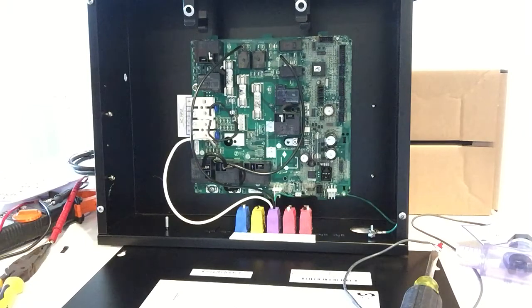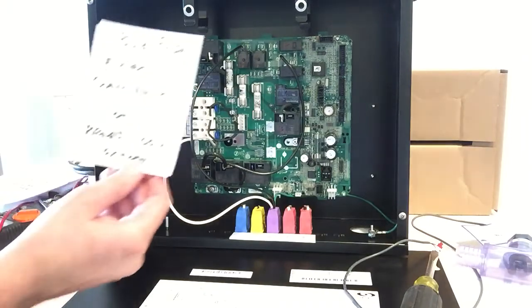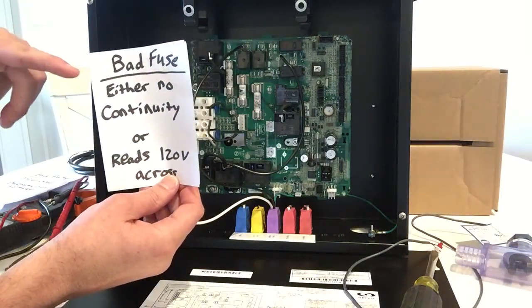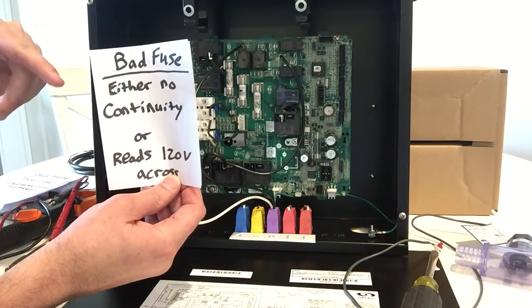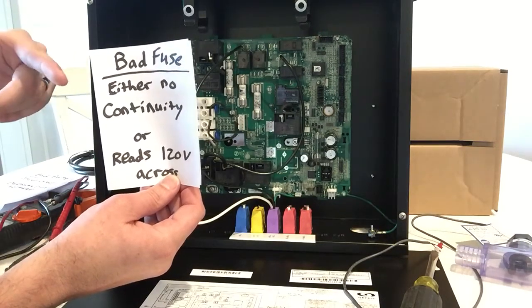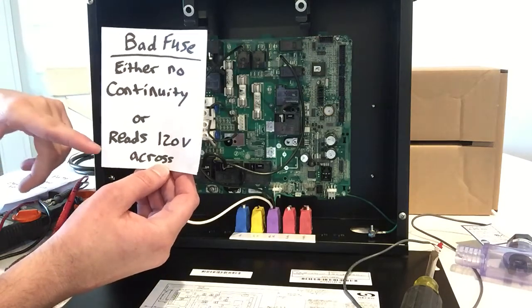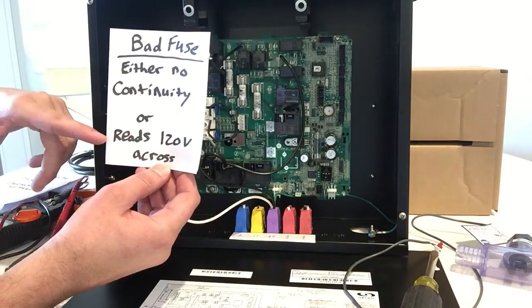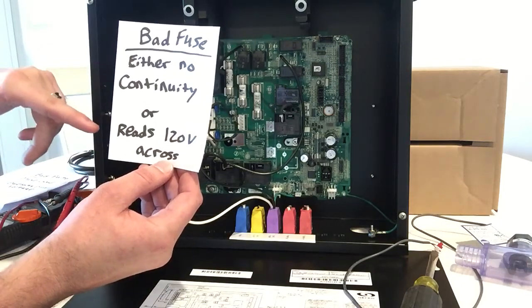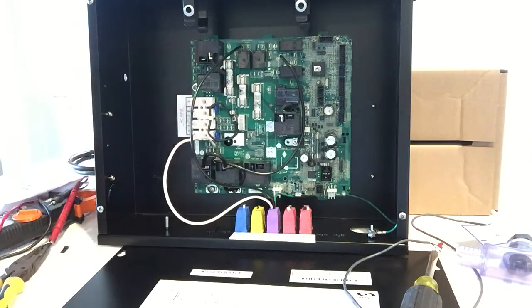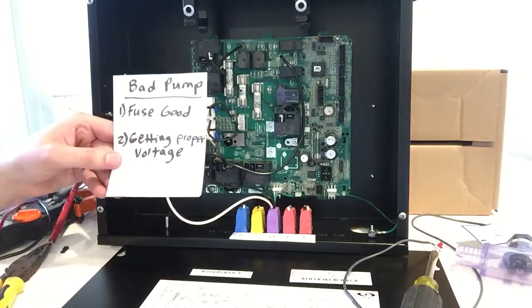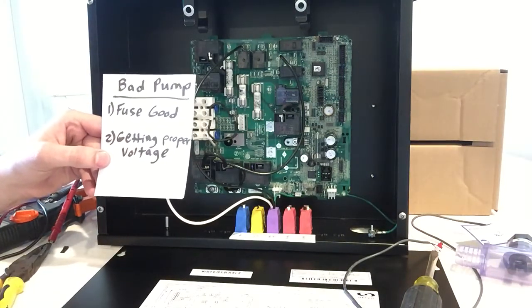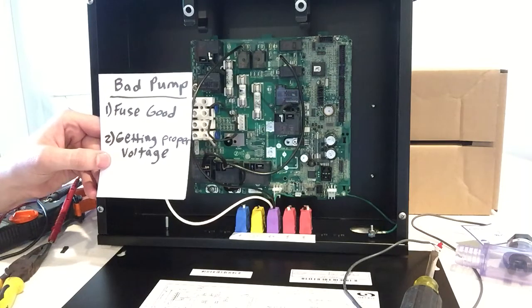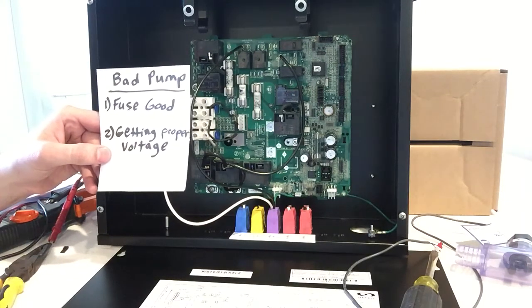So yeah, just to go over it again, if your fuse is bad, it's not going to have continuity, which some people's meters have the ability to check, but if you know what you're doing, you'll know what I'm talking about. If you don't have that, then just do the voltage test on it. So, if it reads 120 volts across the top and bottom, the fuse is bad, replace the fuse. If the fuse is good and your circulation pump is getting proper voltage, but your pump is not running, your circulation pump is bad.